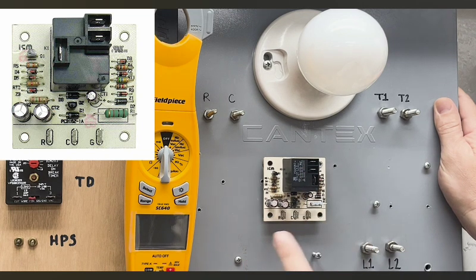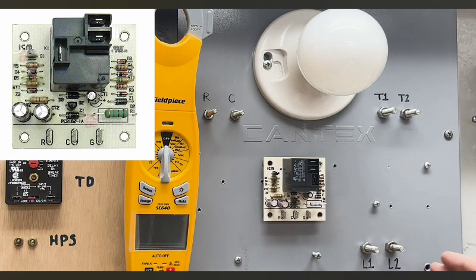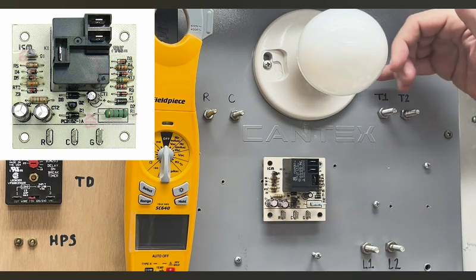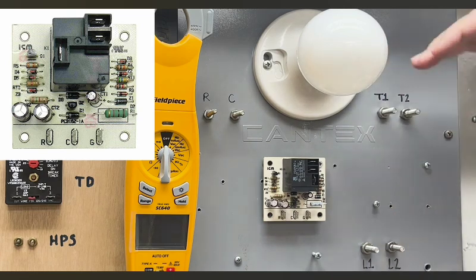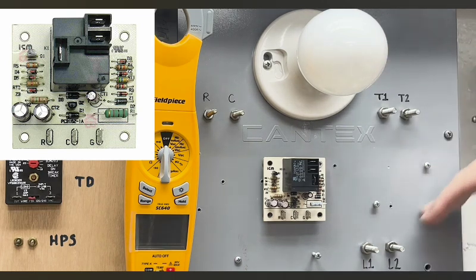Now, as I said in all our other videos, the control boards always have to have 24 volts at all times because they are a working load. Getting into it, we have the Cantex box here. We have R and C, which will provide our 24 volts that we're going to need down here for the control board. We have L1 and L2, which is a realistic power supply of 240 volts, just like we have in the field. And as you can see up here, we have T1 and T2, and we have to put that 240 volts up here, breaking it across the relay, one of those legs. And once we do that, we can get our load to come on.